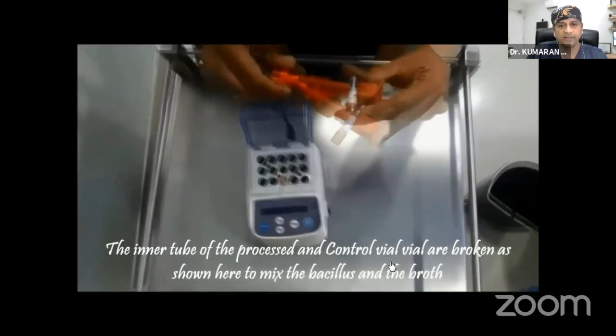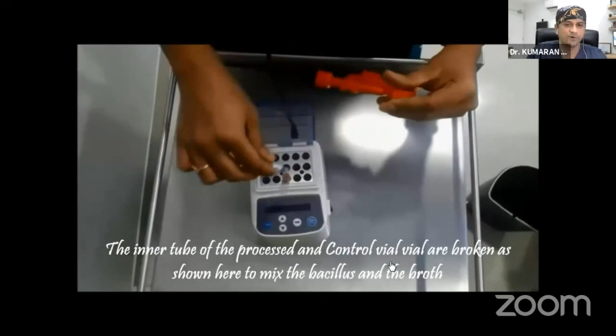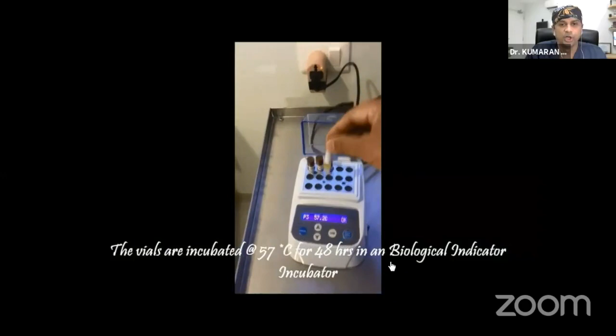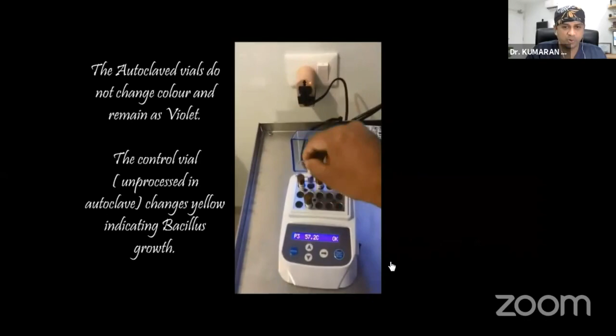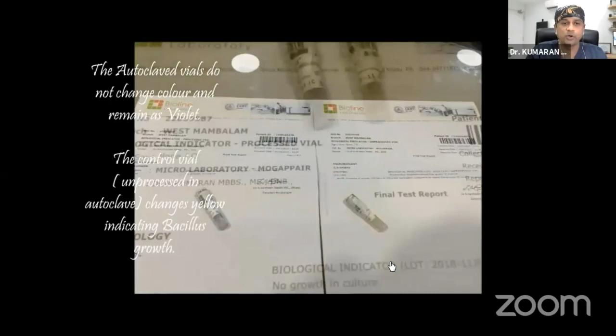The inner tube is broken as shown here, and they are incubated in a biological indicator incubator at around 57 degrees Celsius for 48 hours. It is very important to break the inner tube, otherwise the whole process is a waste. So after they are incubated, you will find the non-autoclaved vial turning yellow, showing there's a growth of the bacteria, whereas the one that is processed does not change in color. This is the only indicator which proves that your autoclave has worked properly.